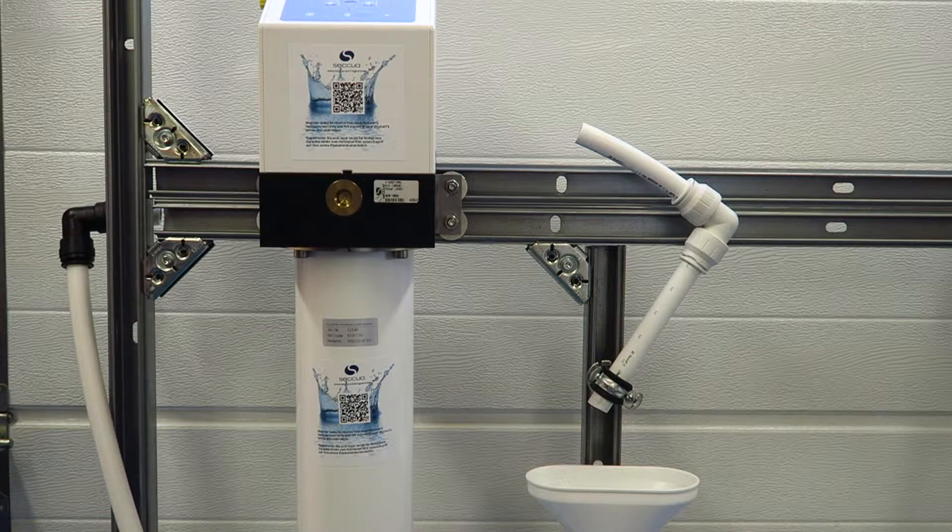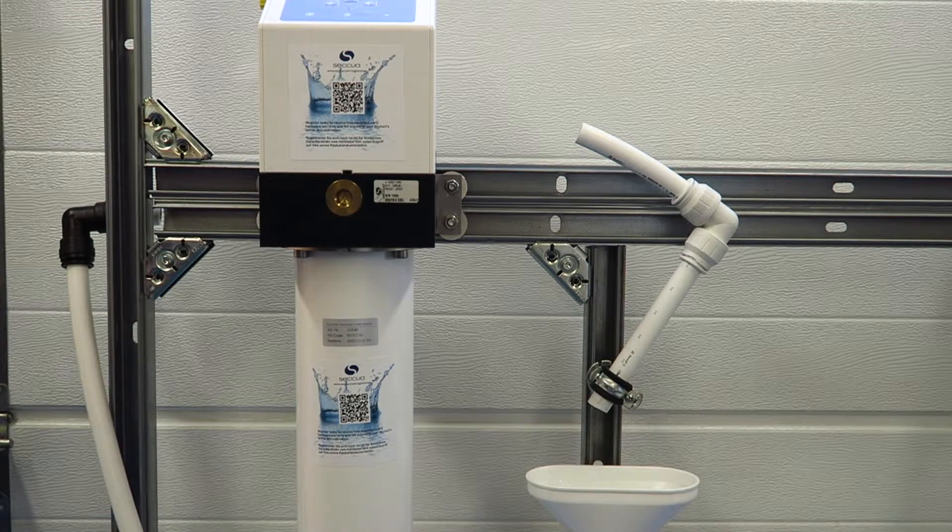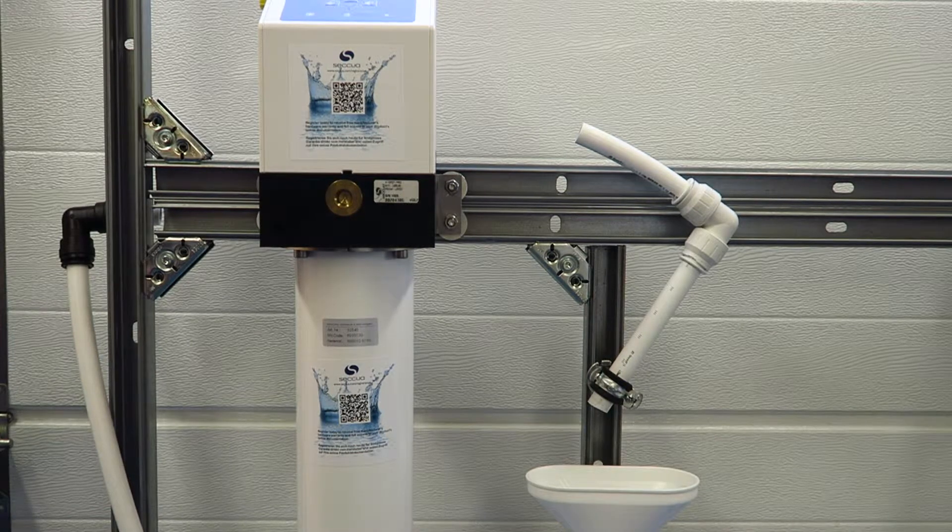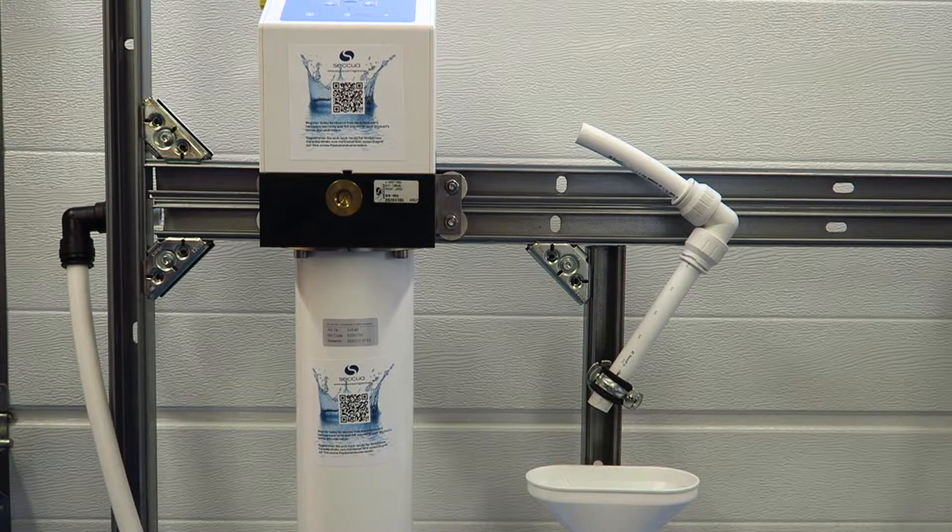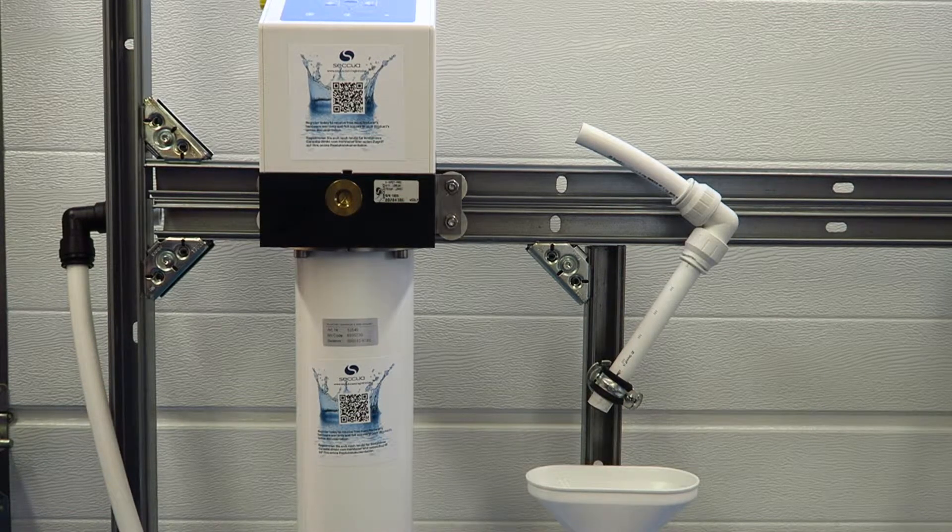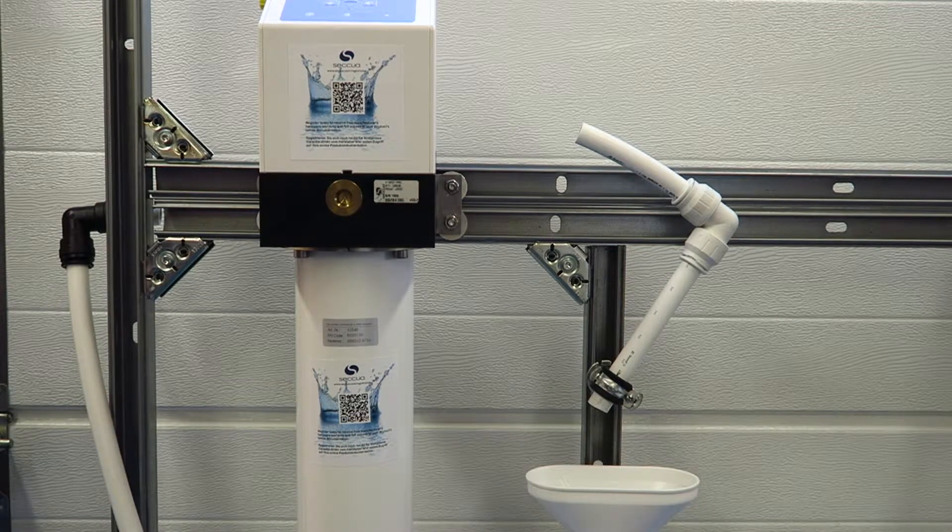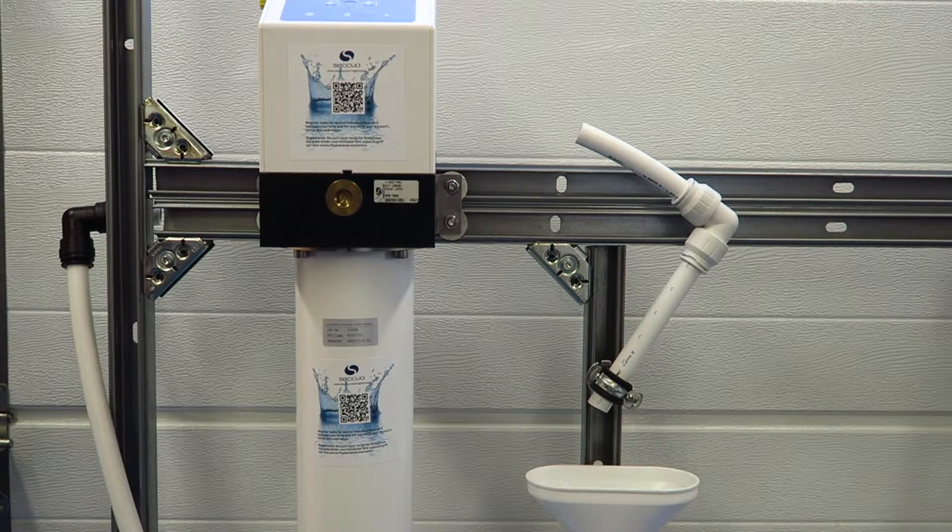Ensure that you have a 100 micron pre-filter installed in the feed line. Depending on your installation, you may need a pressure reducer in the feed line, as the max operating pressure of the Yule Spring is 5 bar or 72 psi.